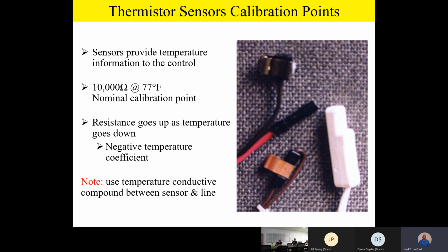Takes outdoor air temperature. Those other sensors are going to be clamped on, you'll notice. There's some other different sensors there. They might be a tube type of sensor. They might be one that just clamps on, with a little copper clamp. It doesn't matter. They all have the same calibration point, and that's 10,000 ohms at 77 degrees.